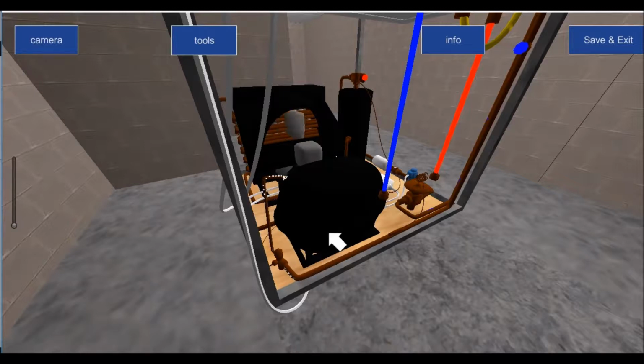And it could be a problem even with your pipe work, that you're not getting enough oil back to the compressor. So you need to consider the job. It's hard for me to say, because your definition of rattly is different to my definition of rattly. Unless we're both standing there listening to it, I can't really tell you what a rattly compressor is. But as I say, usually it's an indication that the compressor's on its way out.